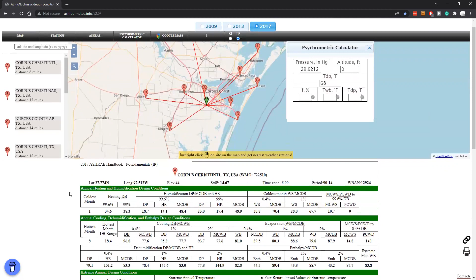So you right click on the map, find your location, click on it. What we normally do is look at your annual cooling, dehumidification, and enthalpy design conditions. We usually use the cooling 1% data—that's our target design for a load calculation, the dry bulb and mean coincidental wet bulb. So those are your design conditions on that 1% day.